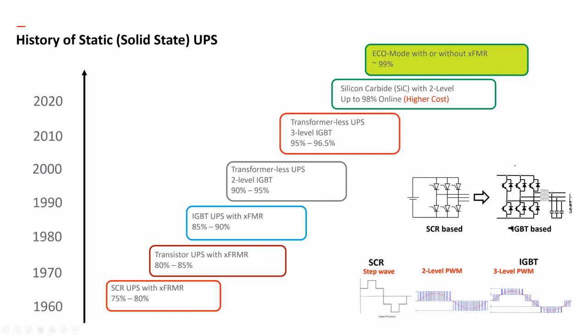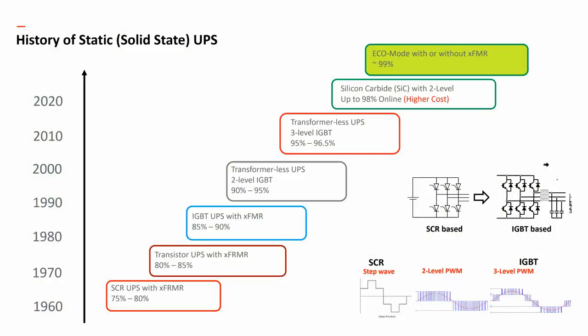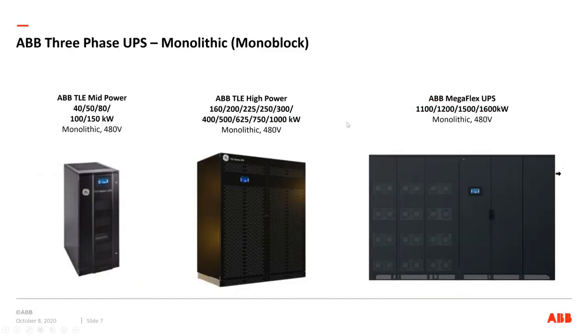And that Megaflex is a unit that is the most modern UPS, designed so that it can operate right out of the gate in a high resistance grounding environment, as I mentioned before, being able to handle a ground fault on the battery. In a solidly grounded environment, with a transformerless UPS, that's only bypass left. So all ABB UPSs, the ones on this slide and the following slide, are what I talked about: three level IGBT based inverters, very high efficiency, power factor corrected in and unity power factor rated.